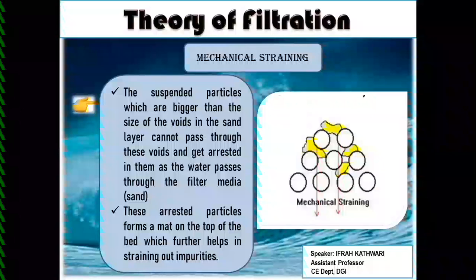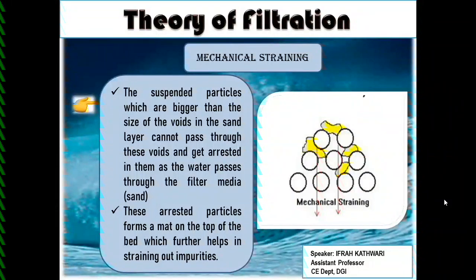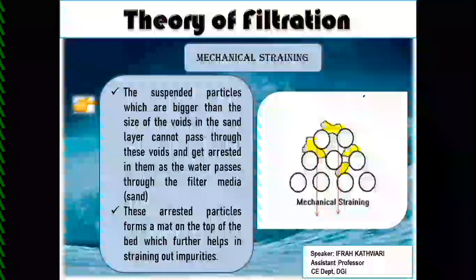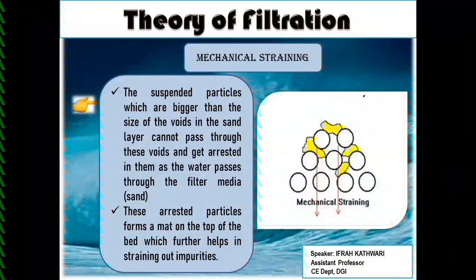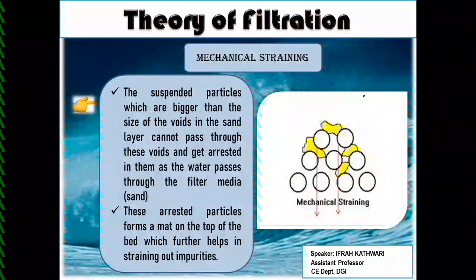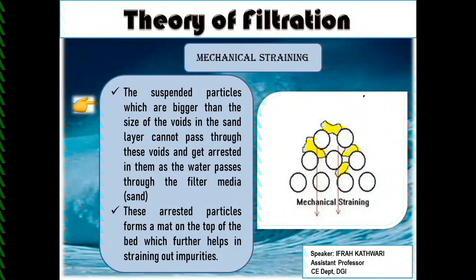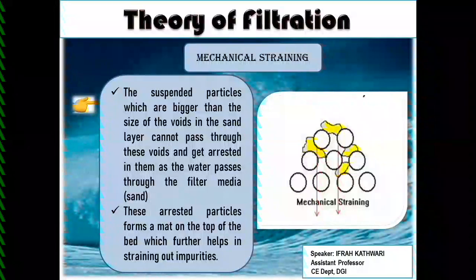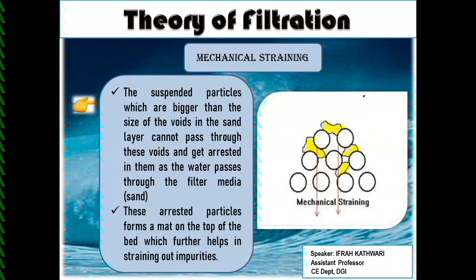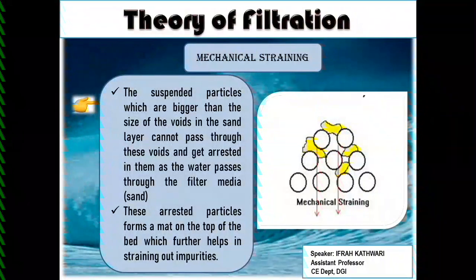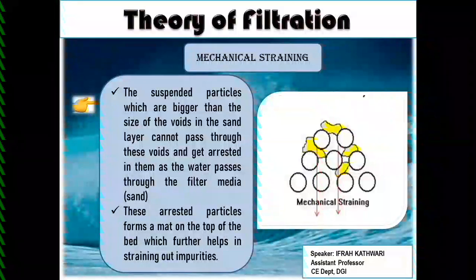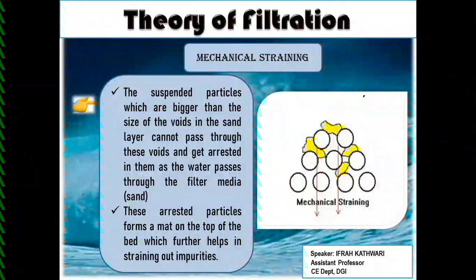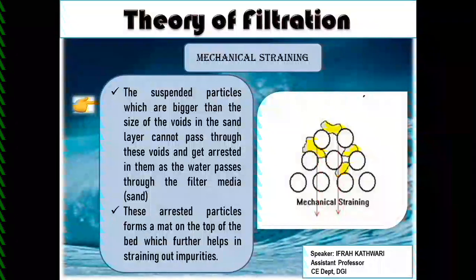As you can see in the picture, the filter media consists of three layers: fine sand, then coarse sand, then gravel. When suspended particles are bigger than the voids present in the sand layer, as sand is perforated, or porous in nature, the bed of sand in the filter media may get clogged by particles which are larger and coarser.